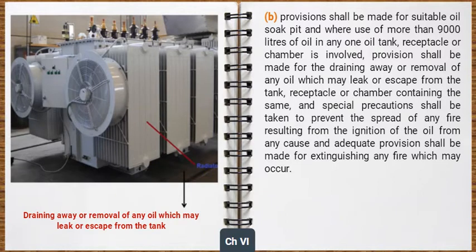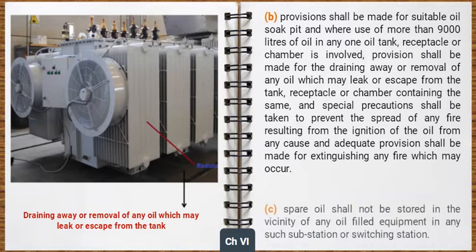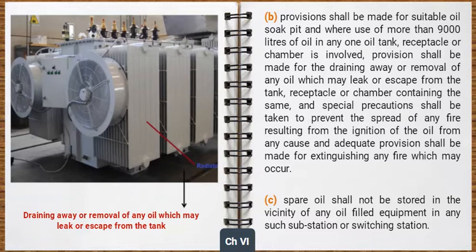is involved, provision shall be made for the draining away or removal of any oil which may leak or escape from the tank, receptacle or chamber containing the same, and special precautions shall be taken to prevent the spread of any fire resulting from the ignition of the oil from any cause, and adequate provision shall be made for extinguishing any fire which may occur. Spare oil shall not be stored in the vicinity of any oil-filled equipment in any such substation or switching station.